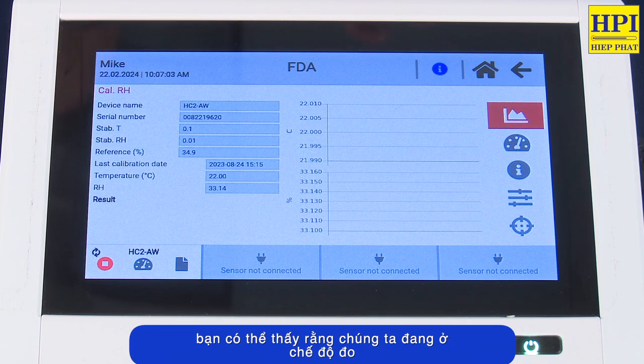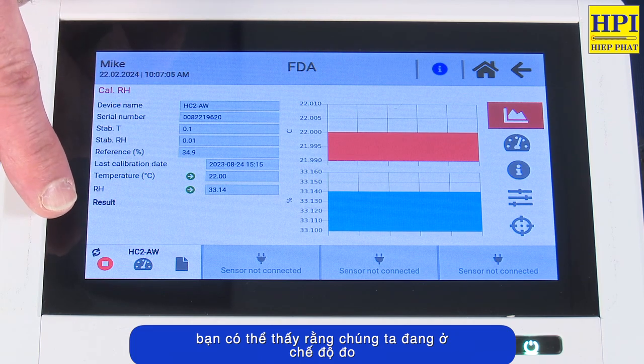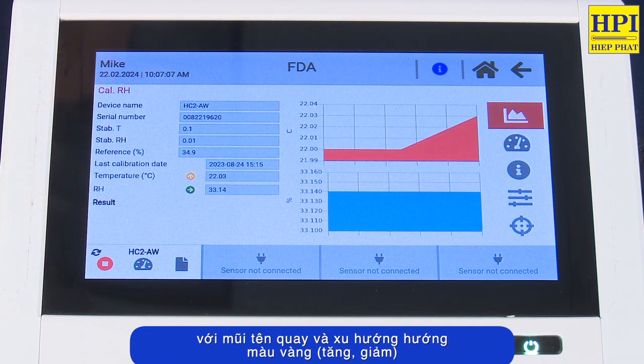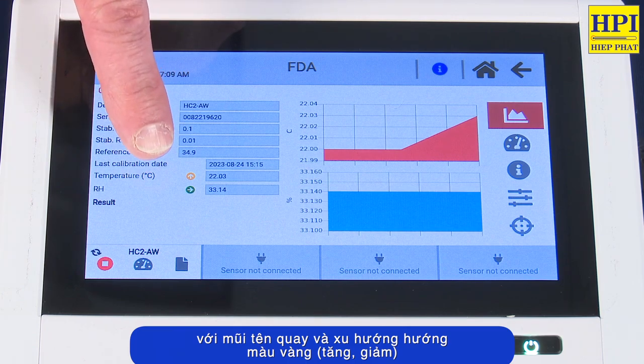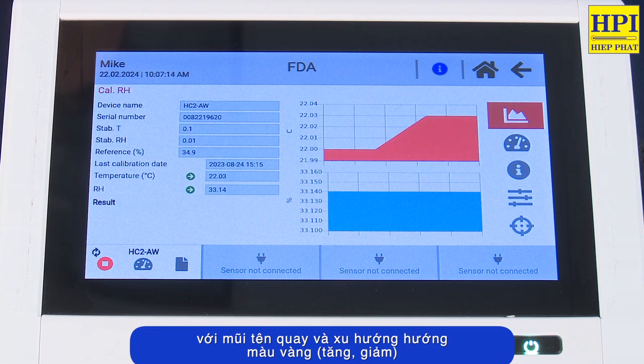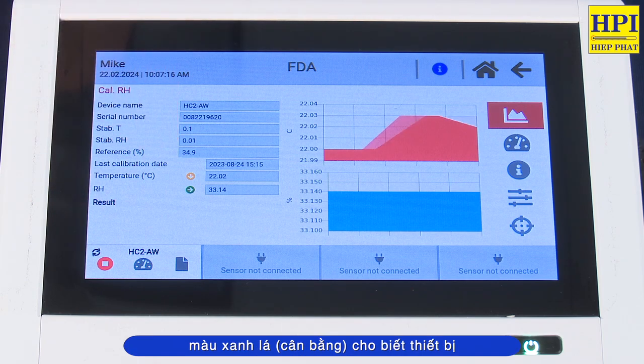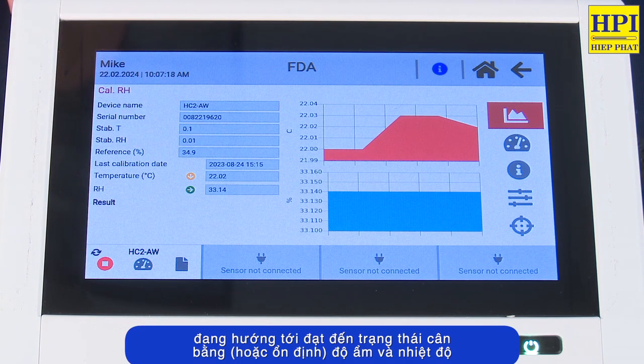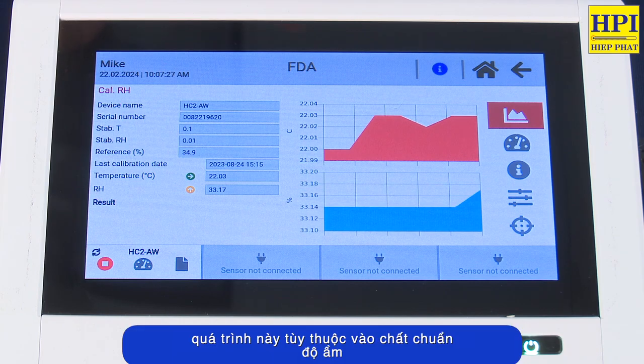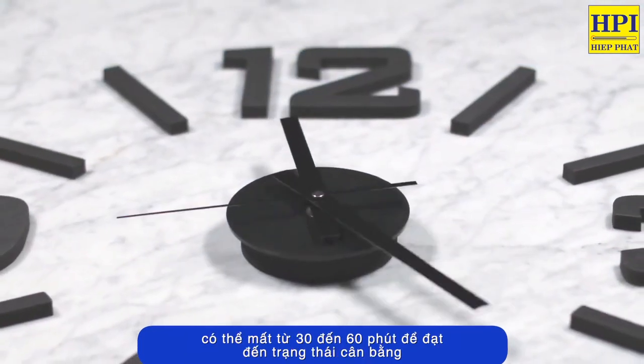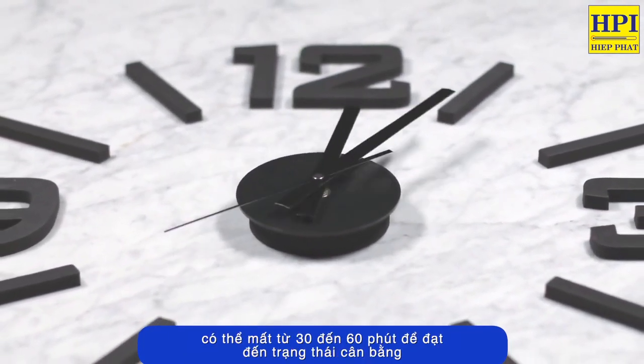You can see that we are in measurement mode by the spinning arrows, and we also have trend indicator bars pointing yellow vertical, green horizontal, yellow downward, indicating that the unit is looking to reach equilibrium or humidity and temperature stability. This process, depending on the humidity standard, can take anywhere from 30 to 60 minutes to reach equilibrium.